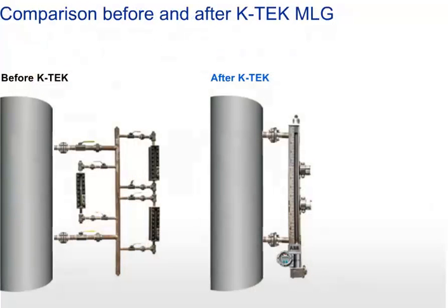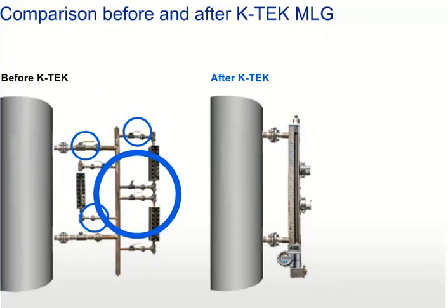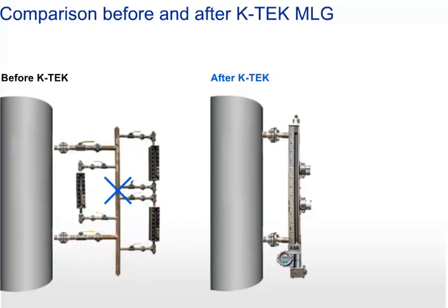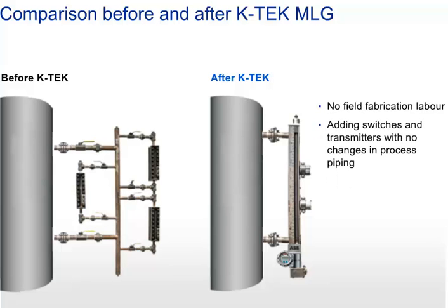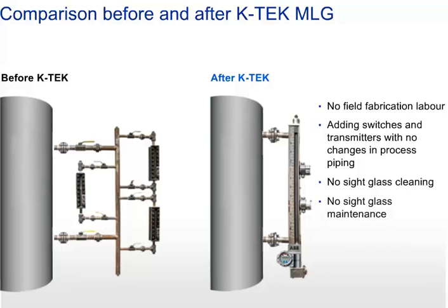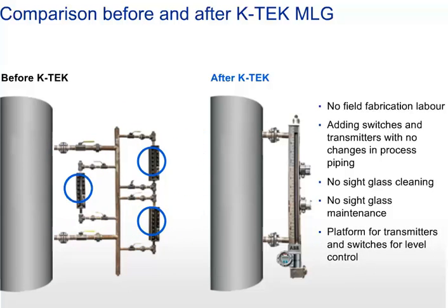Additional MLG advantages and cost savings include: continuous, highly visible level reading; fewer potential leak points for reduction of potentially hazardous fugitive emissions; simplification of design and installation; field fabrication labor is eliminated; switches and transmitters can be added with no changes in process piping; no longer need sight glass cleaning, and maintenance is virtually eliminated; start-up is simplified; sight glass bolt re-torquing to stop leaks is eliminated; and sight glass spare parts inventory and maintenance is eliminated.